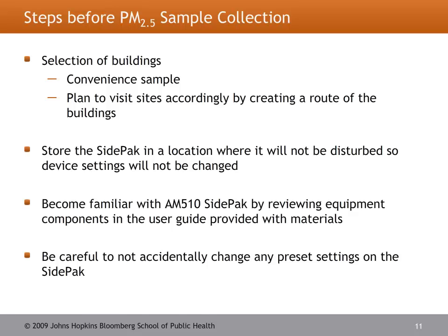In addition to becoming familiar with the materials and how to operate the SidePak, you do want to be careful not to accidentally change any of the preset requirements that are put onto the machine, especially if you are borrowing it from another institution. Generally, the instruments have been calibrated or set to certain standards to collect the sample in an appropriate manner. So you just want to be aware of these settings so that when you are familiarizing yourself with the machine, you don't accidentally change them. If you have any questions, you can always contact local support personnel for further assistance.